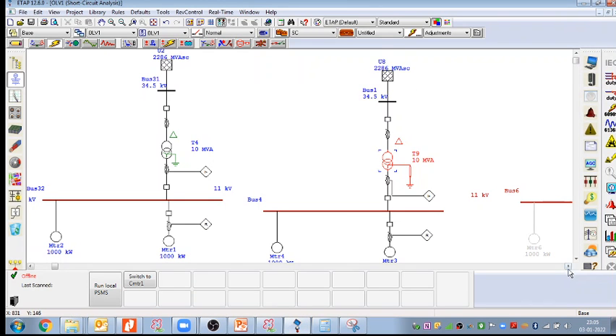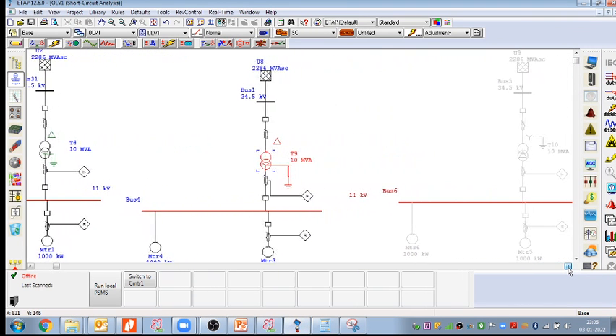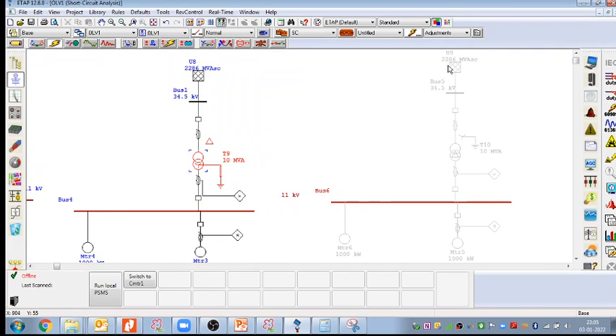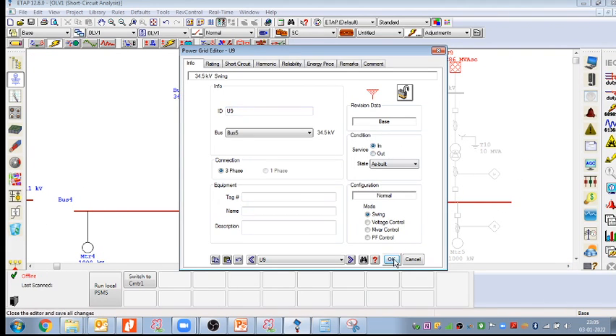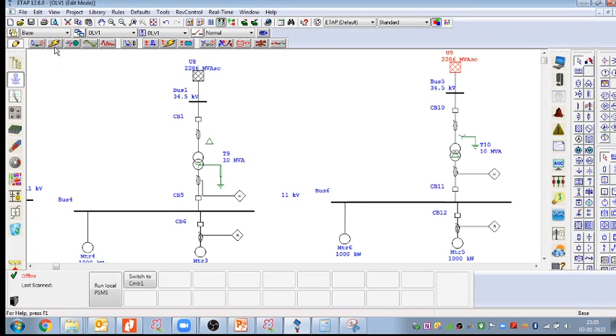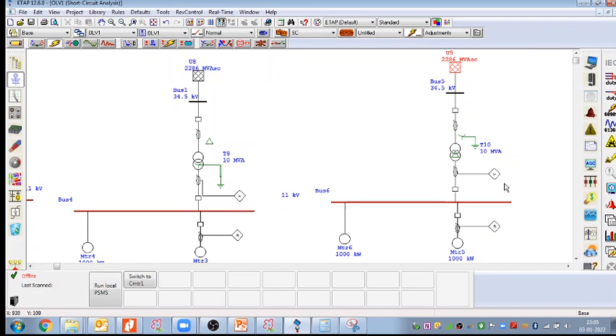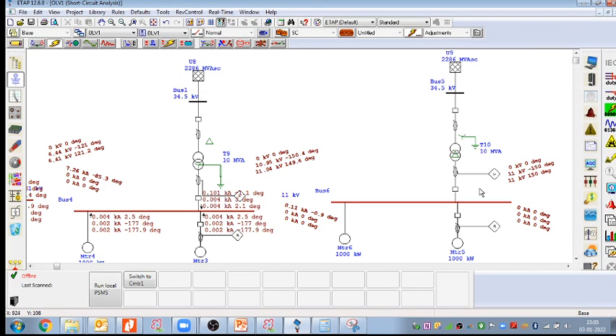I mean to say, how to achieve grounding in a delta connected transformer. My transformer is delta. Here we have the star and this is my delta. If I run the line to ground fault current in a delta connected system, if my winding is delta, the fault current here is coming 100 ampere, here 7.26 kiloampere, but here 0 kiloampere is coming. So how to sense that fault current when the transformer has delta winding, that also we'll discuss in the next session.